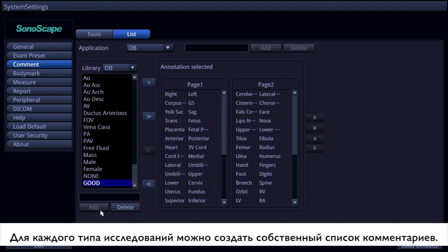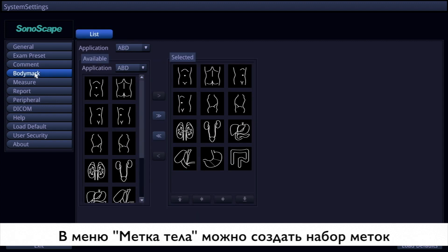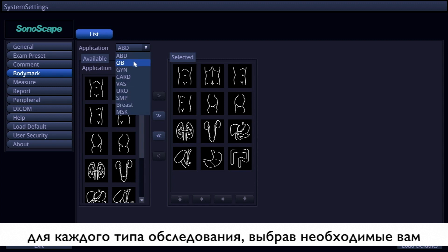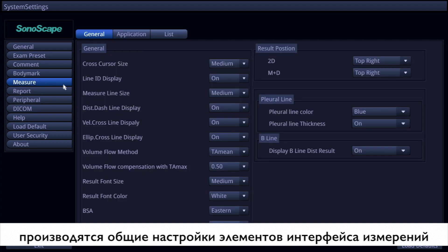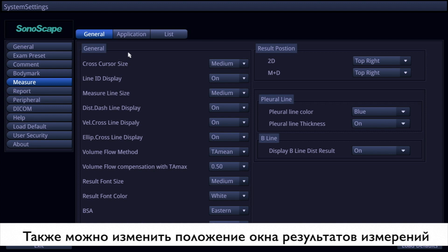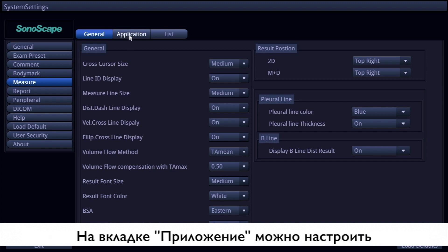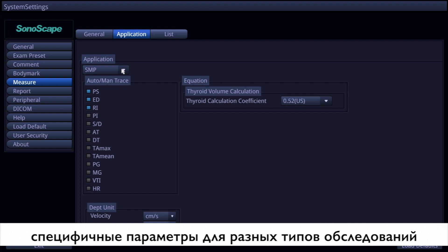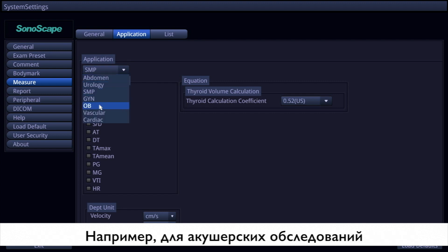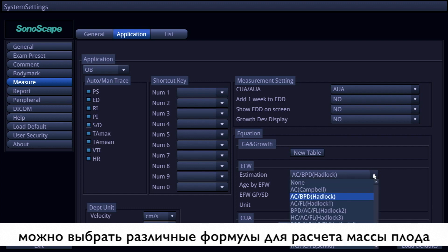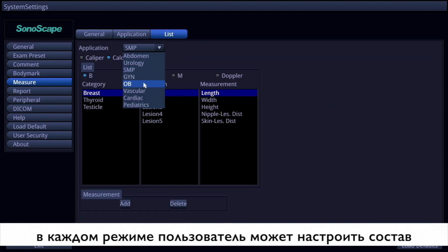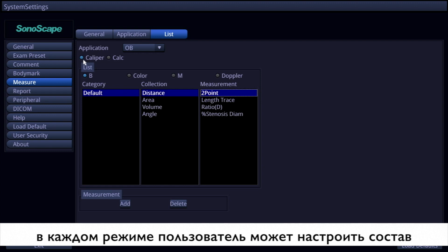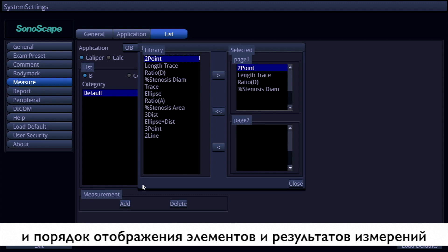You can also add your own comments to the list. The body mark item is similar to the common item — it lists the available body marks in different applications and you choose those you need. There are three pages under the measure item. The general page covers universal settings of measurement elements, including result position. On the application page, you can make specific changes per application — for example, in OB application you can choose different estimations for EFW calculation. On the list page, the call-out methods for calipers and calculations under different applications are adjustable, and adding measurements is also available.